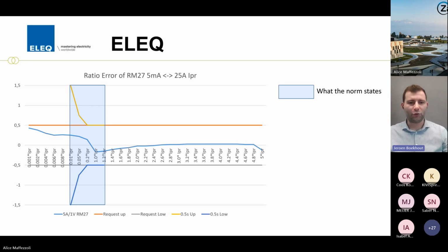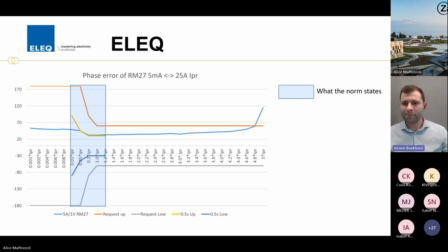If you look at the ratio error, you can clearly see the phase angle at 5 amps primary shoots out of the agreed request. This is simply due to the core not being big enough. If we had gone for a bigger core, we could have gone for a wider range, but then we might have had more impact on the lower side.